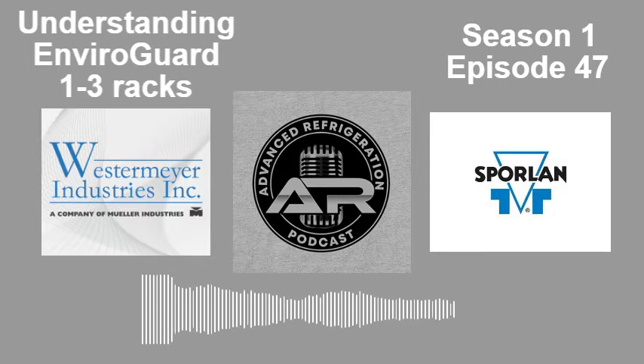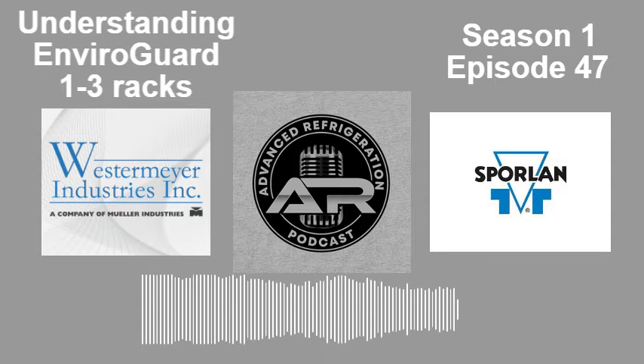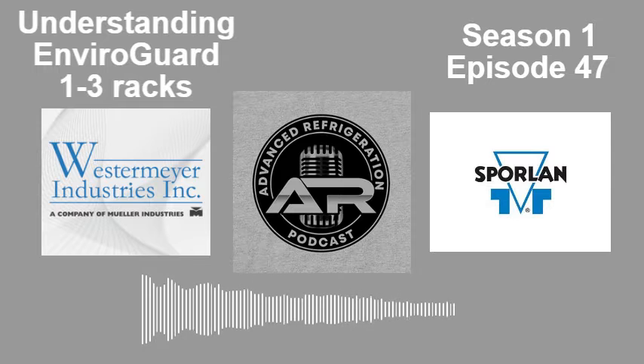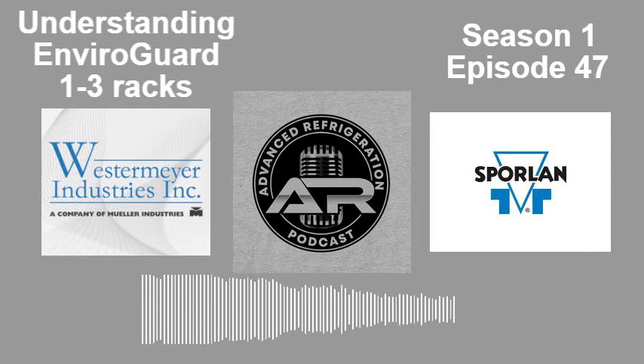Like I said before, now we're not looking at ambient subcooling, we're looking at drop leg subcooling. You still want to look at ambient subcooling because it tells you how well you're doing with your condenser and how your gas charge is doing. On a properly working Enviro-Guard, you should be within 2 to 3 degrees of outside air. What's the TD tip so the guys know what they're looking for? Typically it's 10 degrees for the low temp, 15 degrees for medium temp. That's what all the condensers are sized for.